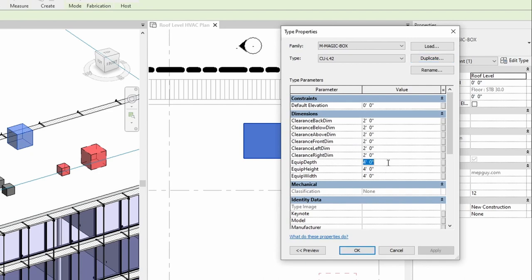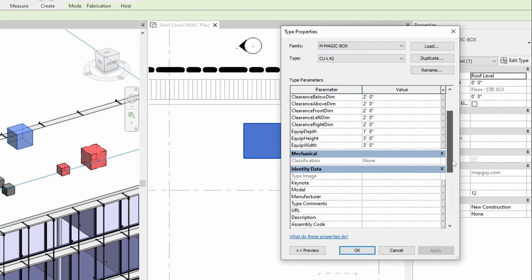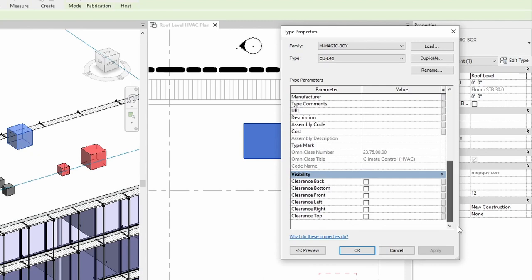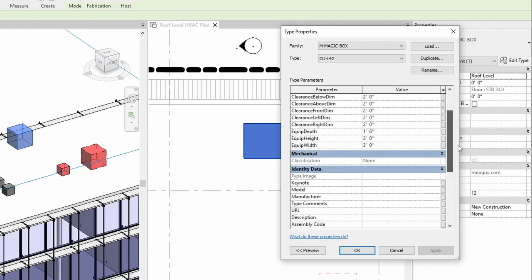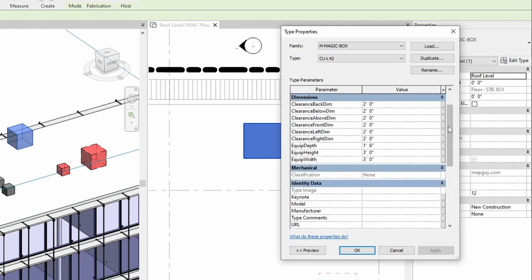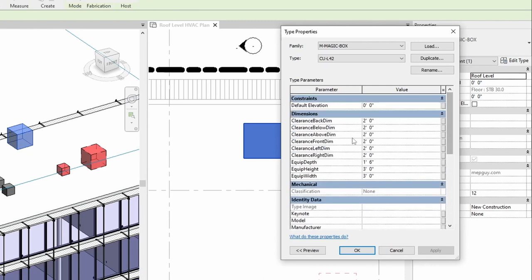Okay, and we're going to change the equipment depth. That's 18 inches. The height is three feet, and the width is also three foot. And I'm going to say that there's a front and a right clearance to this, and I want those dimensions to be, let's see, front clearance, let's also make that 18 inches. And then the right clearance, I'm going to make that, I'm just going to make that six inches.